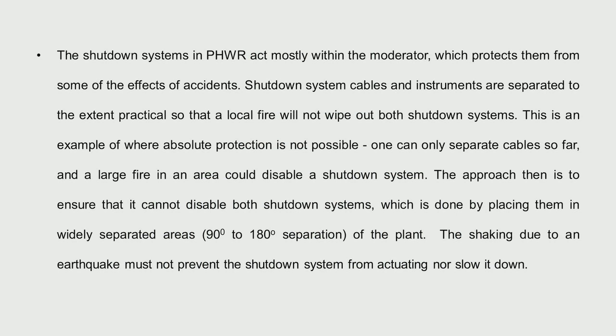Take the shutdown systems of a PHWR. The control rods are in the moderator, and the poison injection system is also in the moderator. Suppose there was a fire near the control rods — we don't want the poison injection system to be affected. So we try to separate them, placing the poison injection system about 180 degrees away. We can use a fire barrier so the fire doesn't spread, but complete independence may not always be possible. Our endeavor is to achieve maximum independence.